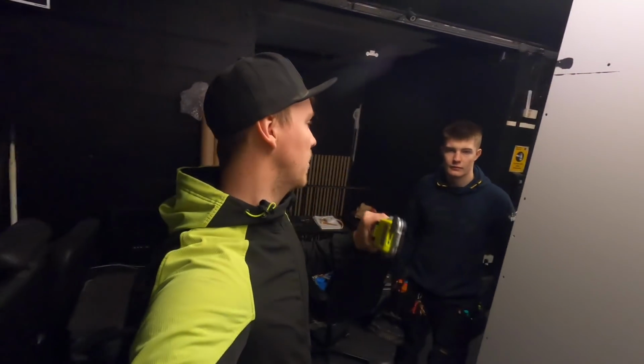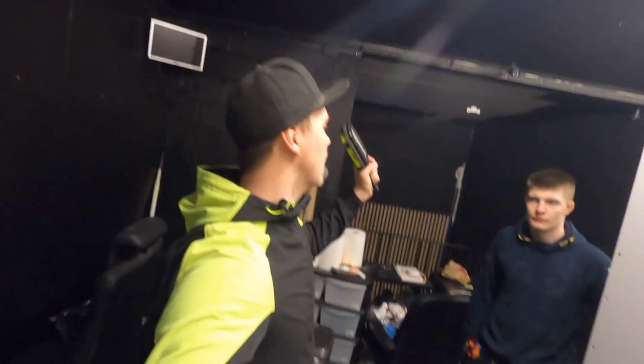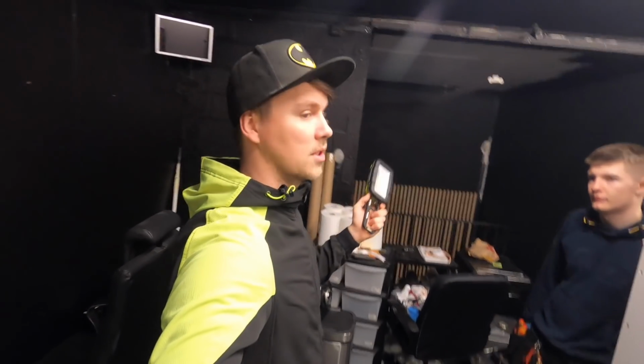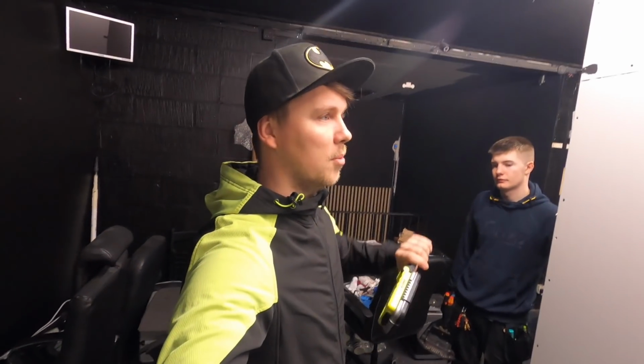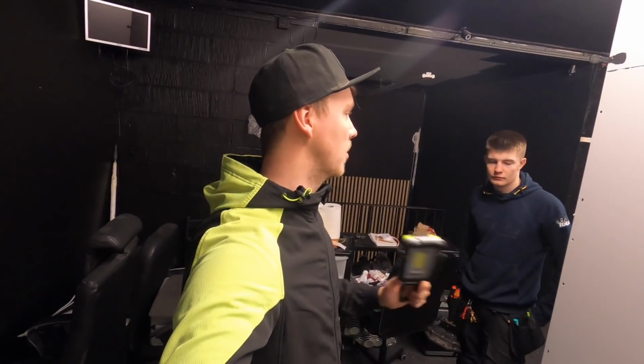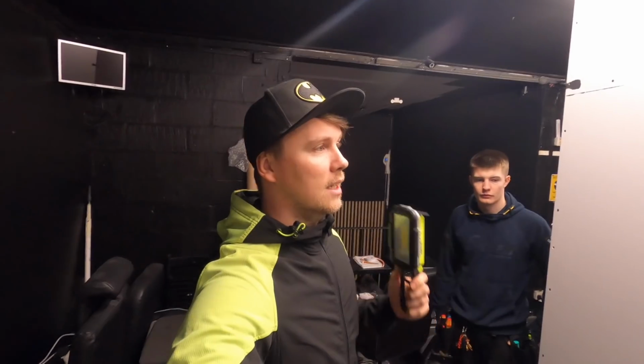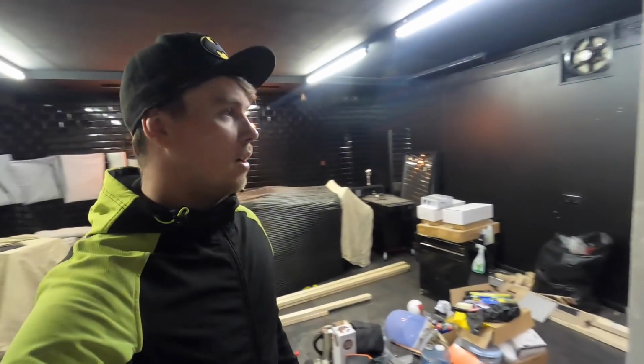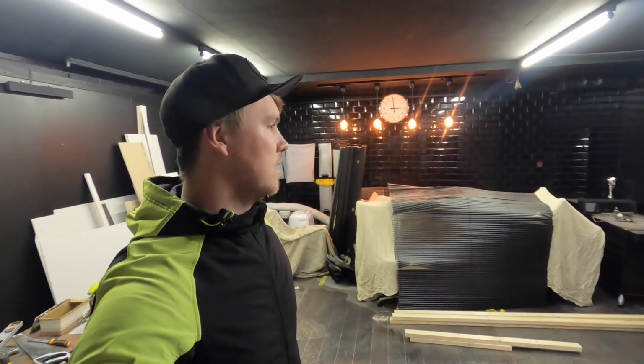So what we're going to do is split. Adam's going to split out the kitchen, what was the kitchen, get rid of them sockets. We're going to derate it to a 20 amp because there is not a lot of draw. The fact there's 4 ring mains, there's also a spare one downstairs that we can use for future. He's going to rip that out. That will then allow us just to tap off a radial for the sockets in here, sockets in here. There's no draw at all. There's just a coffee machine here and a fridge. There's no kettles, there's no anything like that. So we can get on with that.